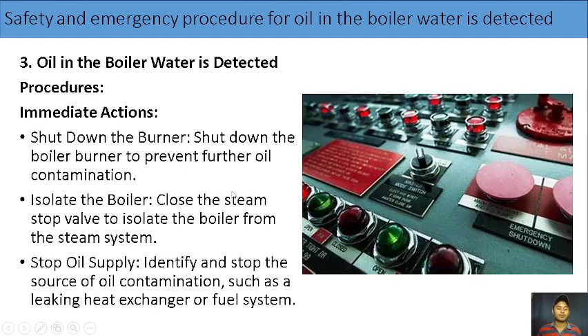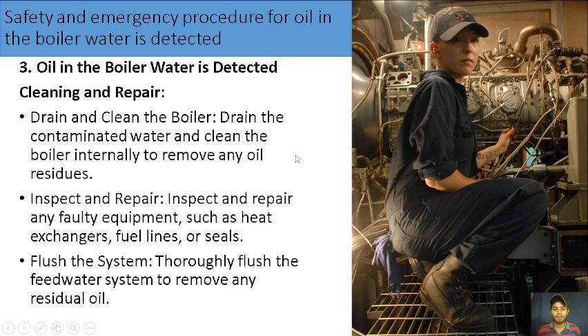So procedures, what will we do? Immediate action: shut down the boiler burner to prevent further oil contamination. Isolate the boiler. Close the steam stop valve to isolate the boiler from the steam supply system. And stop the oil supply. Identify and stop the source of oil contamination, such as the leaking heat exchanger or fuel system.